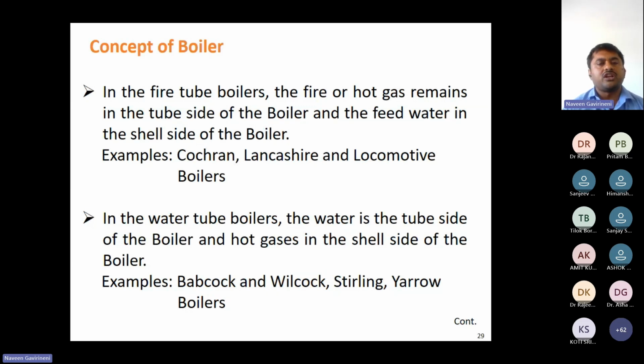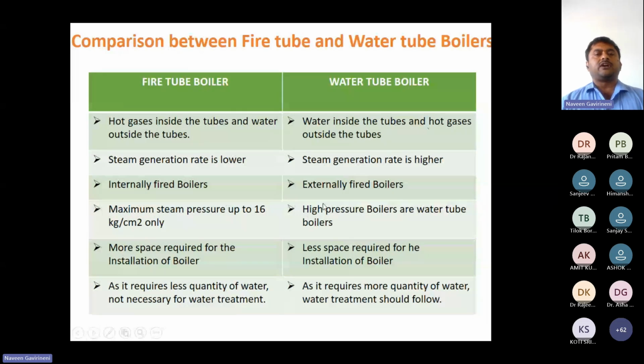The main concept: fire tube boilers and water tube boilers. As you know, in a fire tube boiler, fire and hot gas are in the tube, and water remains outside the tube. These are the types of fire tube boilers. In a water tube boiler, water is inside the tube and flue gas is outside the tubes. These are the major differences between fire tube and water tube. Up to 16 kg per cm square only we use fire tube. For higher pressures we use water tube. All supercritical boilers and big plants come under water tube boilers only. So these are the major differences.